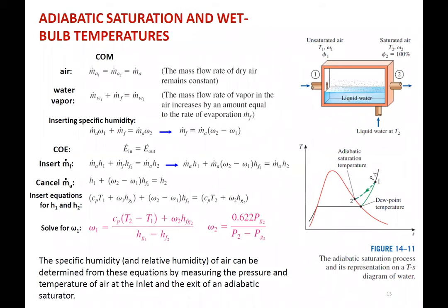All right, one extra derivation is the wet bulb temperature, okay? And it is basically a measurement of, we have to have methods of how do we measure humidity, right? We have to get a relative humidity. How do we measure that, right? Usually we either measure a dew point temperature, or we measure a wet bulb temperature, and then from there calculate a relative humidity. We don't typically measure relative humidity directly if we want a very accurate measurement.